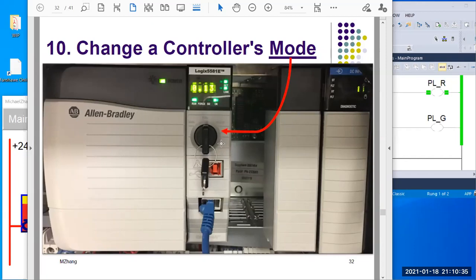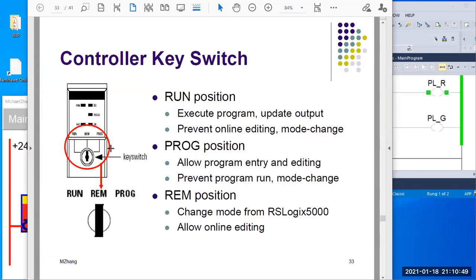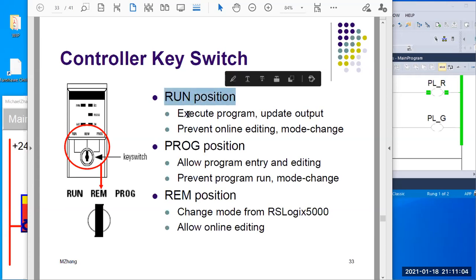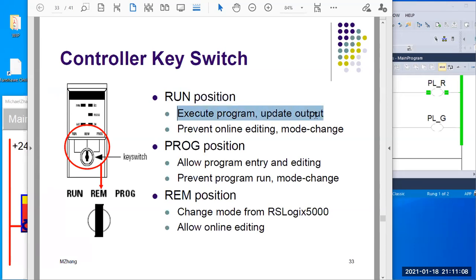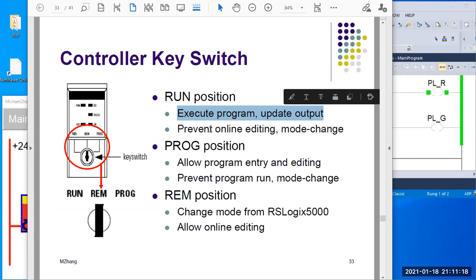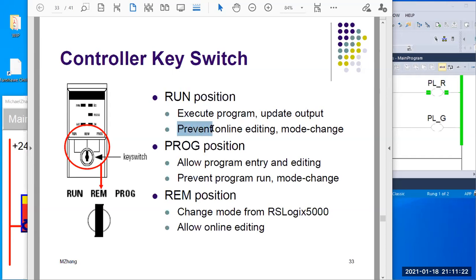Normally, this is how you change the PLC controller running mode. You have three different choices, and that's physically. Let me explain more details on these three different positions. If you put it into run position, the program will be executed. The output will be updated — that means turn on and turn off, doing exactly what you expect from the program. Also, because it's in run mode, that prevents online editing, so nobody can change the program when it's running.